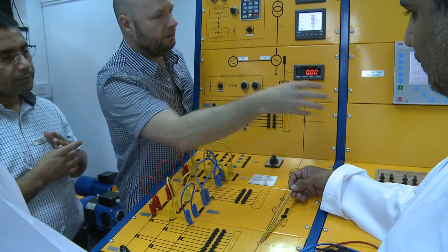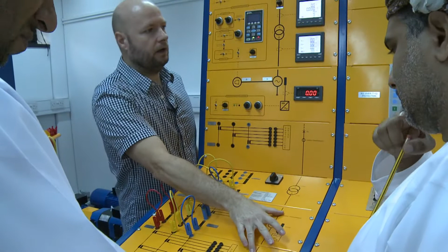So in this particular unit, we don't have a second protection here, so these are not used, you have to short them, exactly. Okay, so we'll short these out, this one and this one, these CTs. But however, in this one, we do have a second relay.